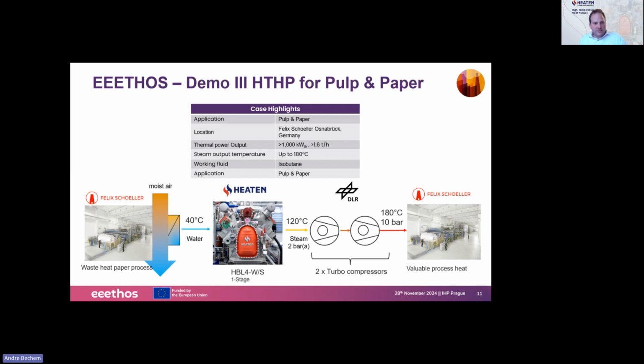The working fluid in this case is isobutane, and we produce directly saturated steam with a pressure of 2 bar. This 120 degrees is then supplied to our partner, the DLR, which compresses it further with two turbo compressors as an MVR.